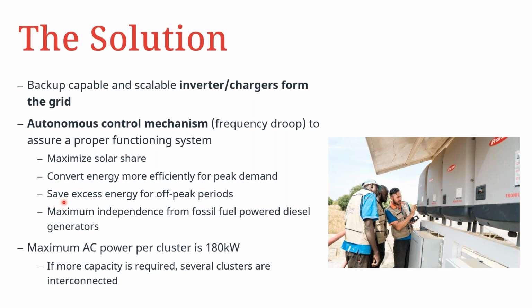You can also, as I mentioned, save the excess energy for off-peak consumption. And then, of course, this allows you to have maximum independence from fossil fuels in the case that you would have to use diesel generators as an example. So for this kind of solution, in an AC coupled setup involving Fronius and Victron inverter chargers, the maximum AC power per cluster would be about 180 kilowatt. And if more power is required, you would have to combine several clusters. In this case, you can build systems that are even above a megawatt in AC power delivery.